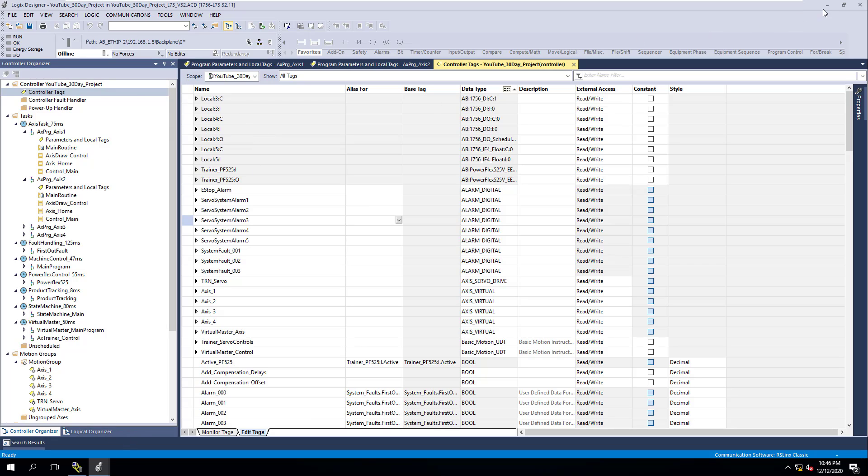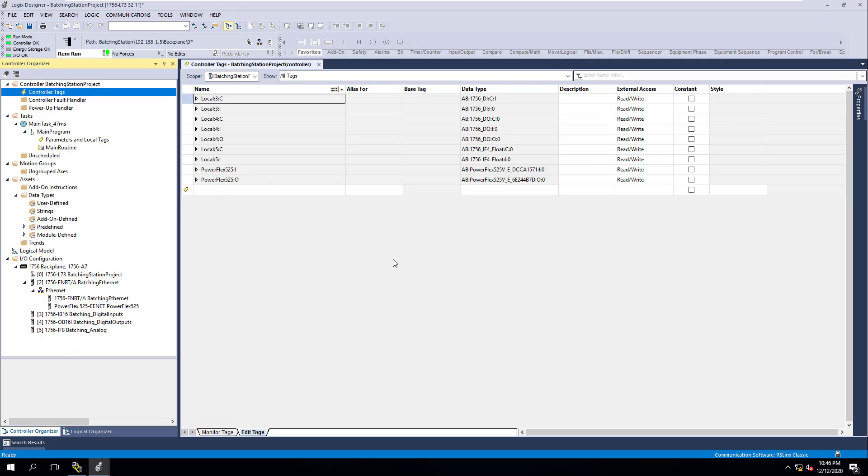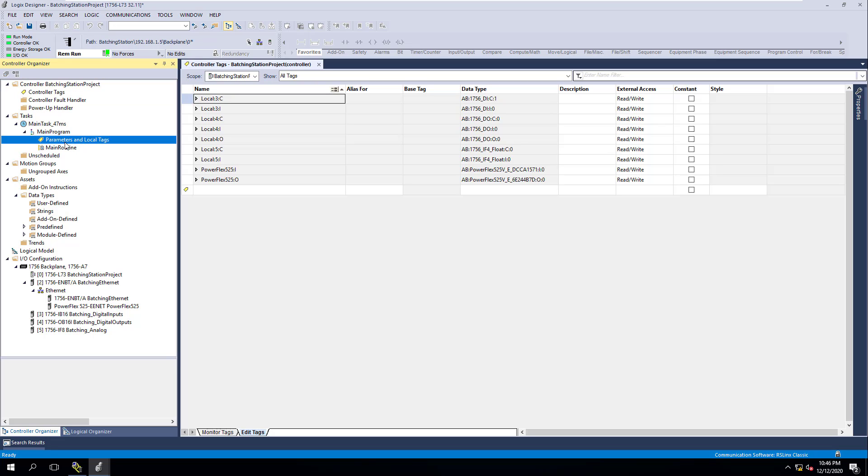I just wanted to kind of break that down and show you that real quick. This is a higher level example. It's very important to understand when you're setting things up. It's very detail-oriented. You can do program level stuff that can be the exact same. You can copy and paste things. But on the controller level, you cannot do that. You can't have multiple tags named the exact same thing. But on the program level, you can have like if I have three or four different programs, I can have the tags named the exact same thing and they will not conflict because they're in different program levels.